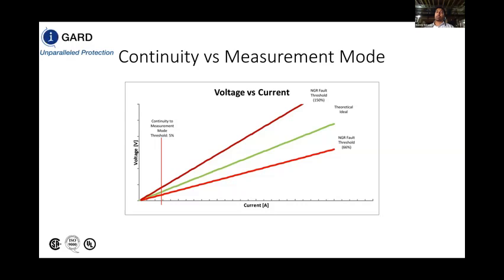As a result, we can compare that measured resistance value with the actual value of resistance that was set at the time of commissioning. And if it's beyond 150% of that value or below 66% of the value, then we're indicating an NGR fault scenario.